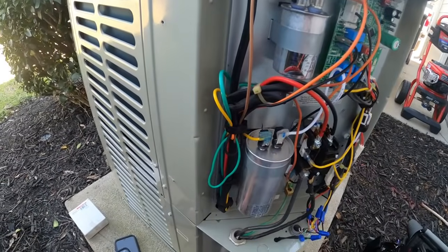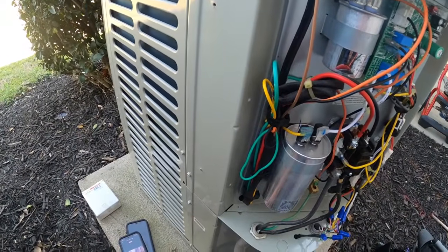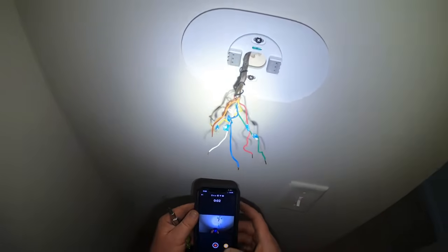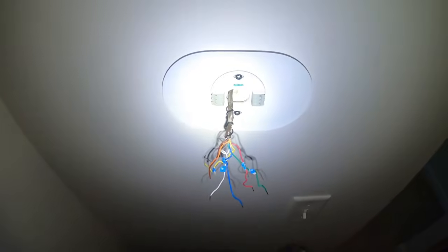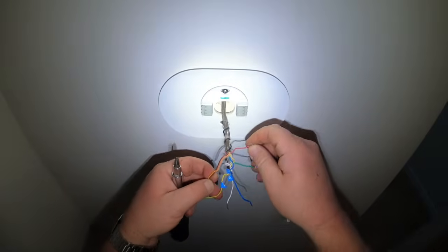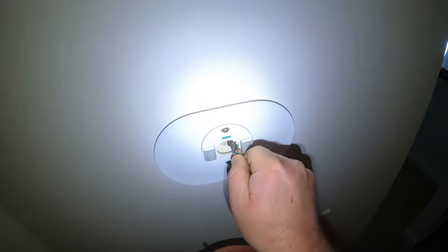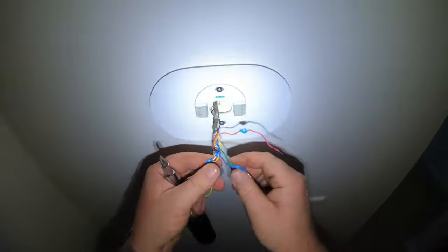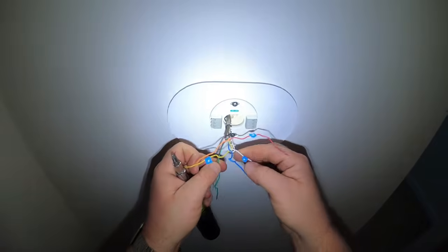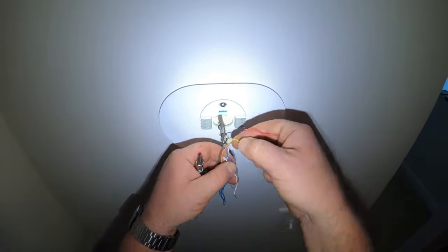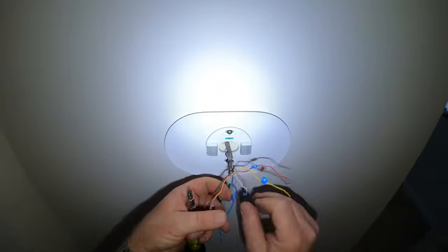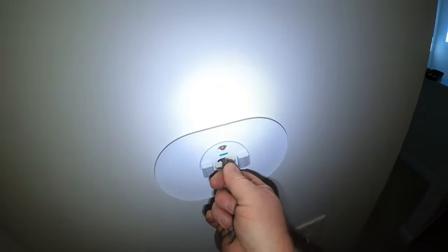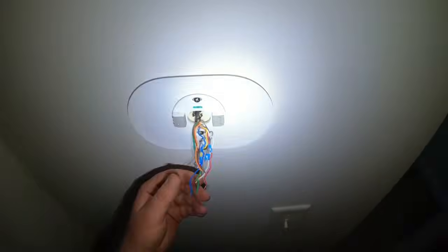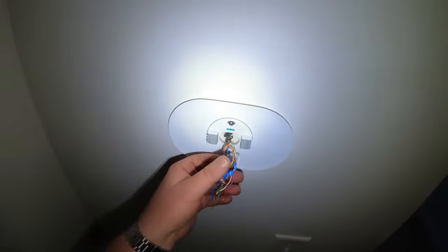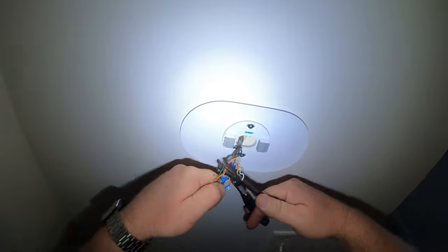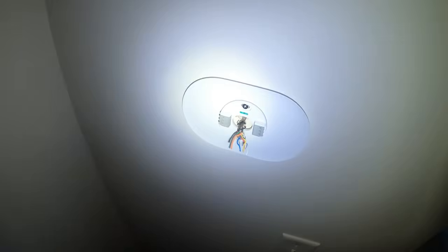So let's go in there now and get that thermostat, or both of those Nest thermostats, wired up right and see what this thing is going to do. So anyway, I don't know what's going on. My camera's acting funny. But anyway, like I said, Nest thermostats have been more of a nuisance problem. I've replaced more of them than I've installed. And I've gone back and replaced ones that I have installed within a year or two sometimes. So they act up. And there's somebody here that didn't pay attention to, I wanted to cut thermostat wire and make it a mile long. You got to cram it behind the thermostat. So here we go. We're just going to trim it off, make it fit.